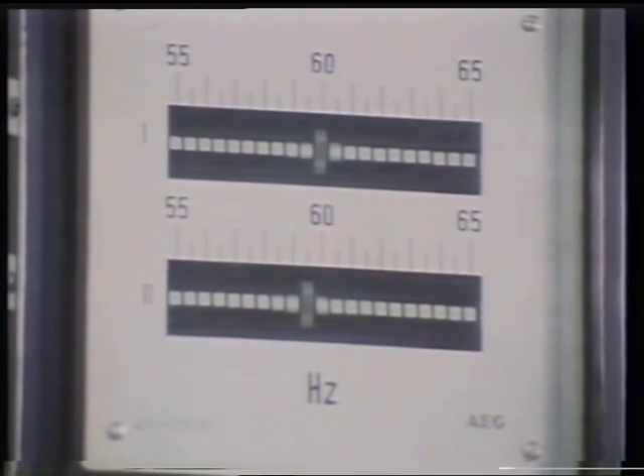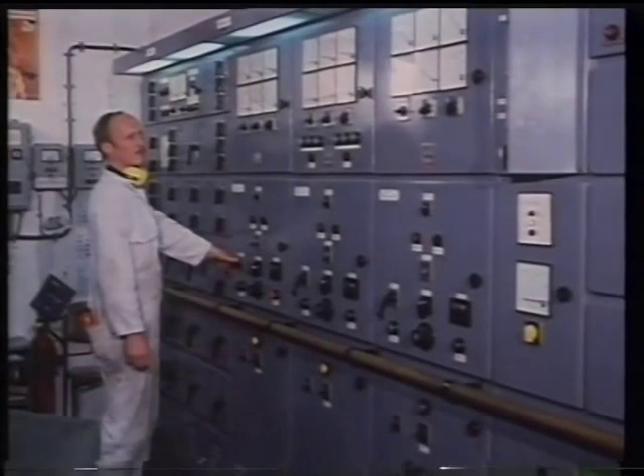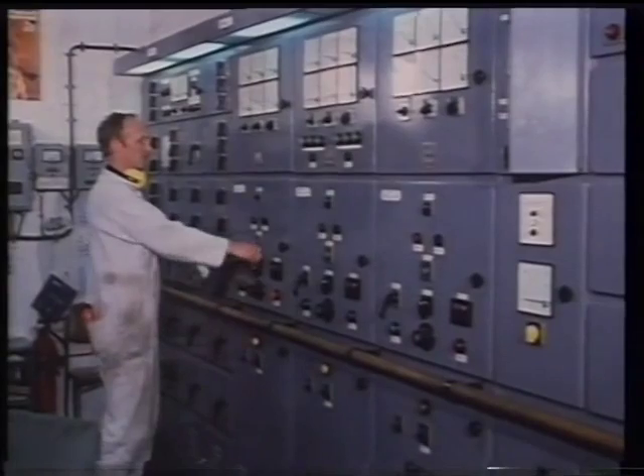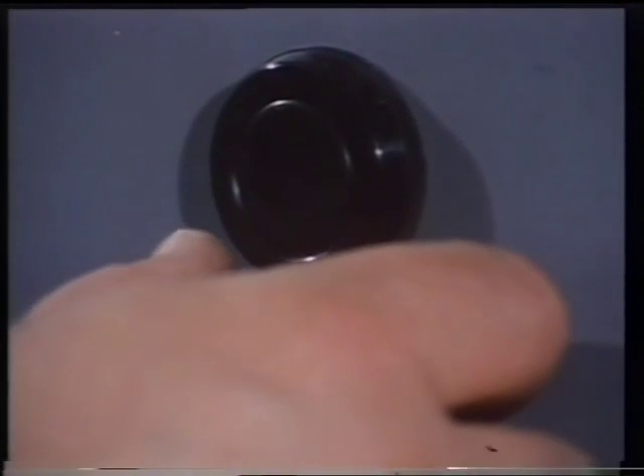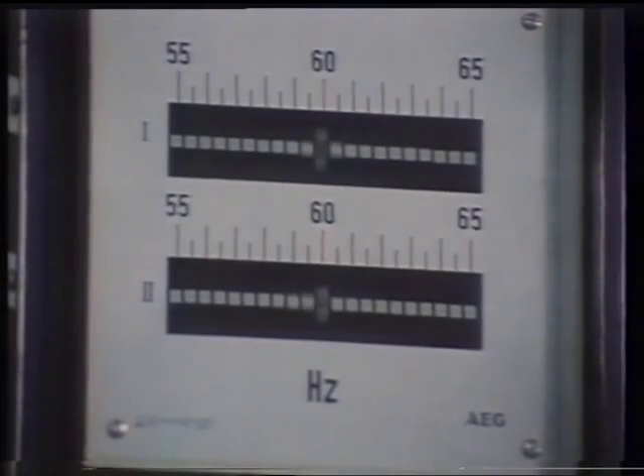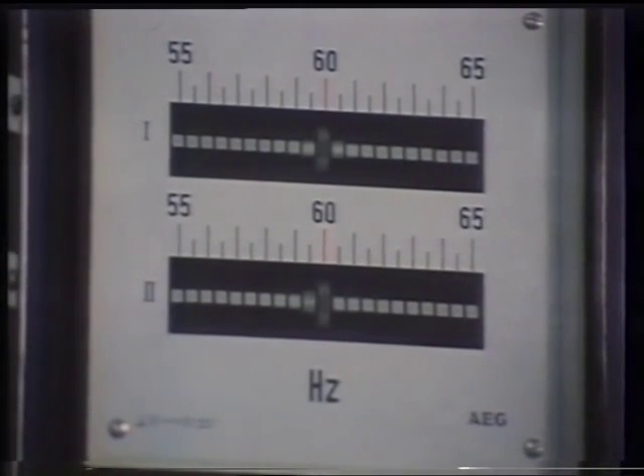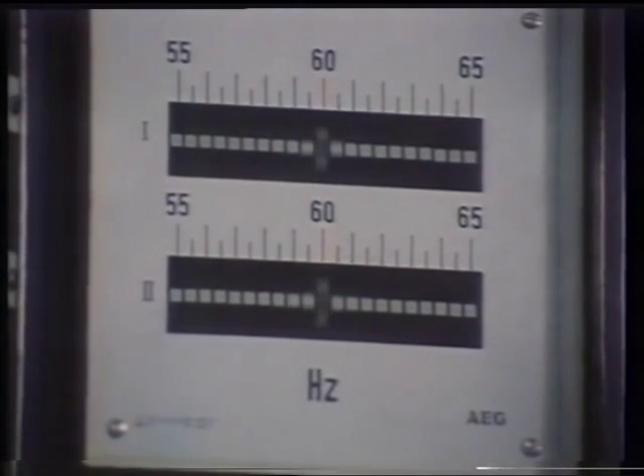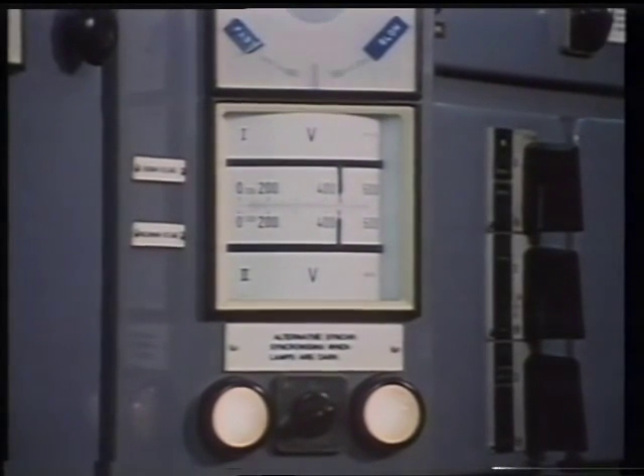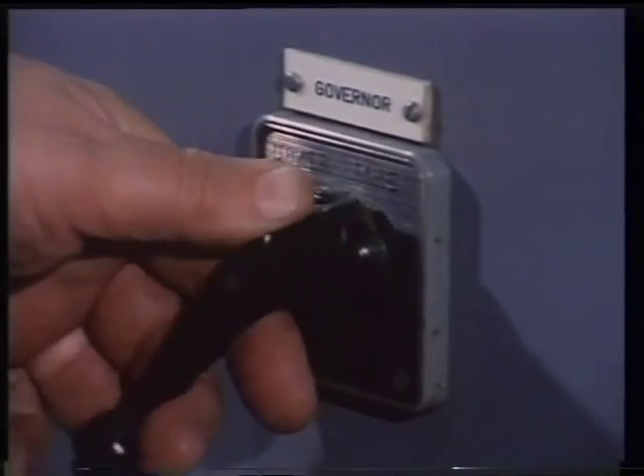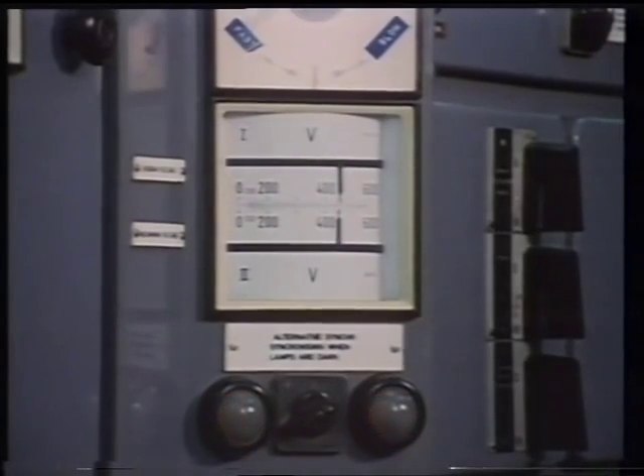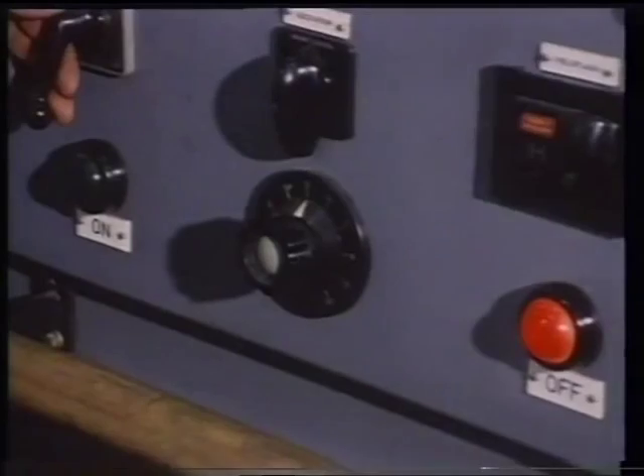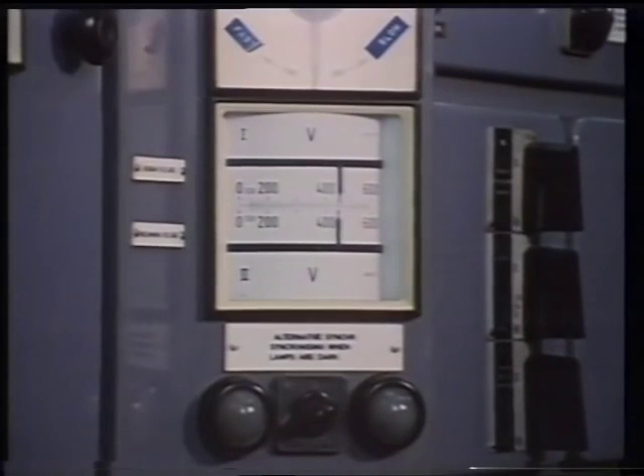Continue adjusting the governor of the prime mover until the frequencies are identical and the phase rotation is synchronized. Here, on the bottom half of the synchroscope, the pointer shows when to close the incoming alternator's circuit breaker. The phase rotations are synchronizing. Now the button can be pressed and the circuit breaker closed. The two alternators now provide power in phase with one another.